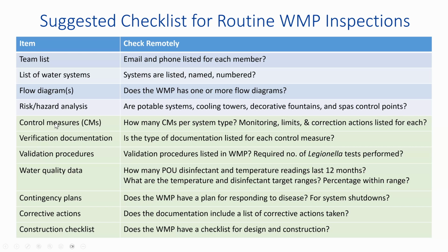But basically, does the water management plan have one? At this point, that's all we're talking about. Does it have a flow diagram? Not anything about it, but just, does it have a flow diagram? And then, is there a risk hazard analysis?